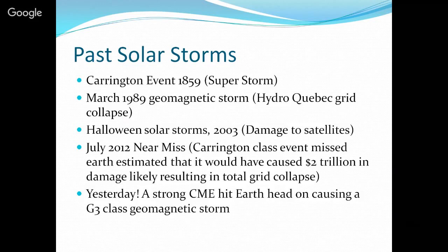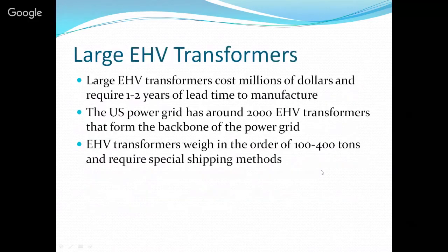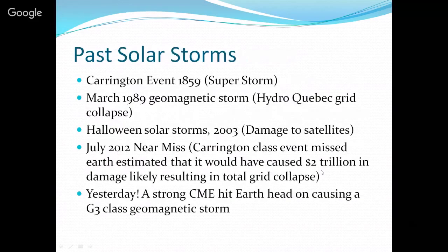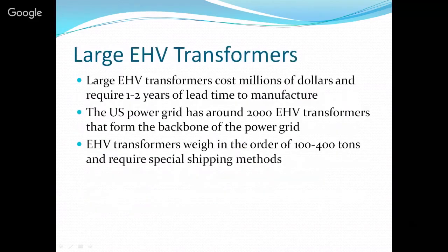So we'll add one more to the list now — that was yesterday. We had a very large X9 class flare from the sun, a big CME, and it's hitting now. Probably not going to cause any damage at our latitude. There's probably going to be some instability issues up north, but since '89 they've really strengthened their grid. They've put neutral isolators on their transformers — DC blocking neutral isolators, it's a way you can get around it. So I suspect we'll probably weather this storm just fine.